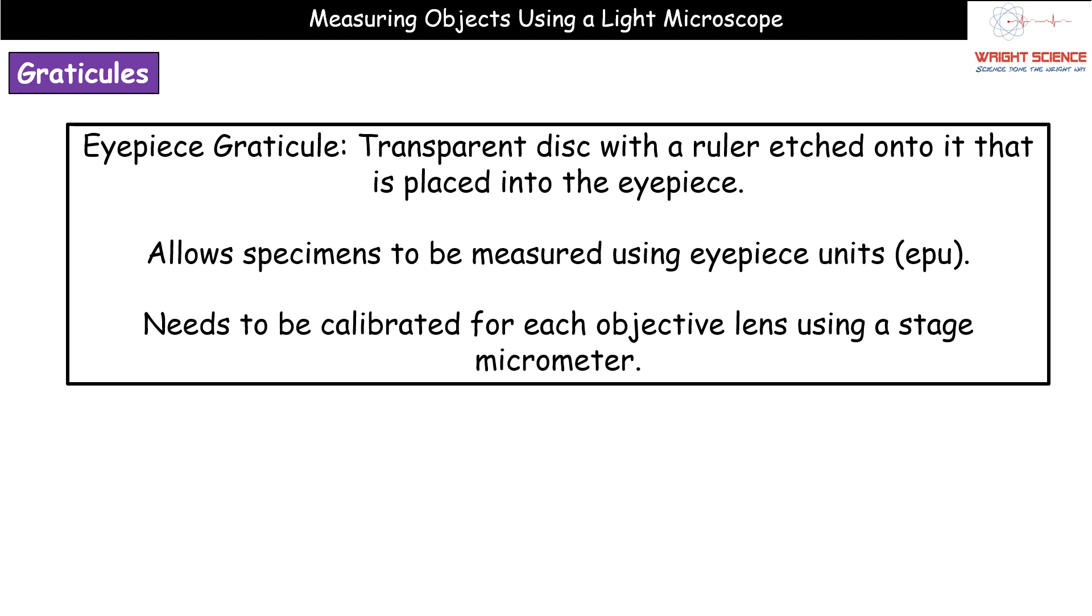As the name suggests from eyepiece graticule, we're going to place that into the eyepiece. What we then have with this little ruler is basically this little scale that's got all these little graduations running through it. That's going to be placed inside the eyepiece itself and these measurements will give us a value in eyepiece units. It doesn't have something like millimeters or anything like that and we'll see why as we go through this video. Each of these little graduations we'd refer to as an individual eyepiece unit.